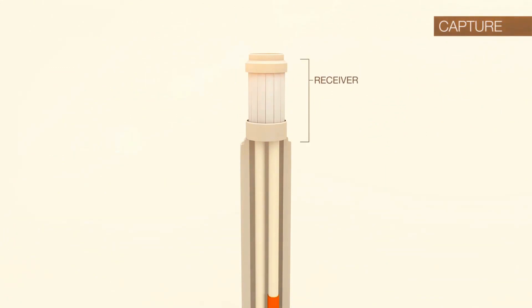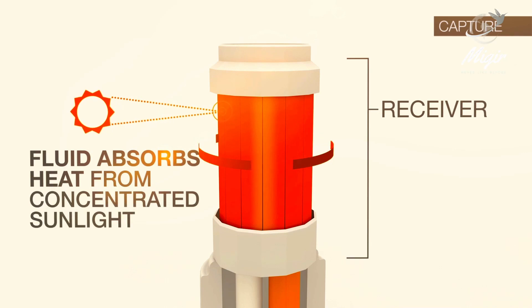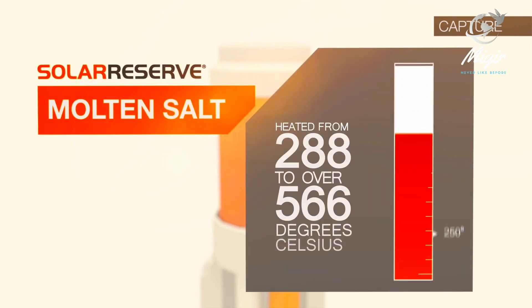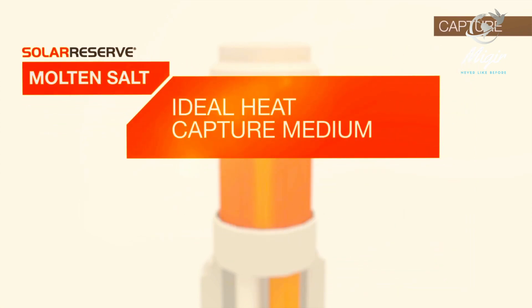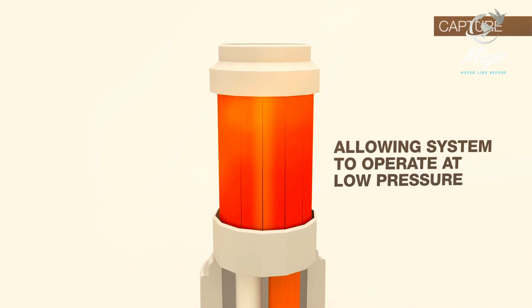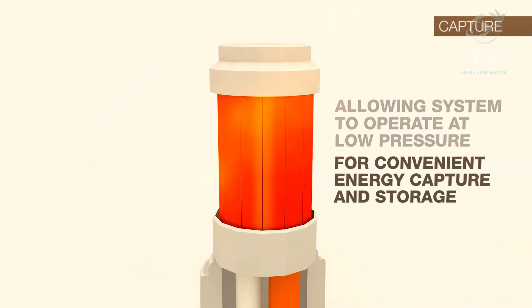Within the receiver, fluid flows through the piping that forms the external walls. This fluid absorbs the heat from the concentrated sunlight. In SolarReserve's technology, the fluid utilized is molten salt, which is heated from 288 to over 566 degrees Celsius. Molten salt is an ideal heat capture medium because it maintains a wider operating temperature range in liquid state, allowing the system to operate at low pressure for superior and safe energy capture and storage.